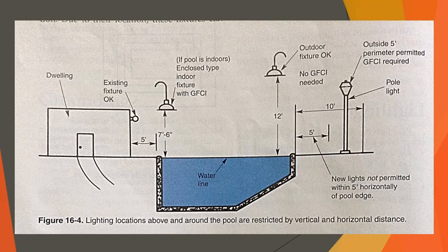The NEC allows existing lighting fixtures to remain as they are, even if the fixtures fall within the otherwise prohibited 5-foot perimeter of the pool side. This is allowed only if the fixtures are rigidly attached to a structure and GFCI protected. Remember, however, that switching of the lights must be located at a point beyond the 5-foot area. This important safety factor should not be overlooked.